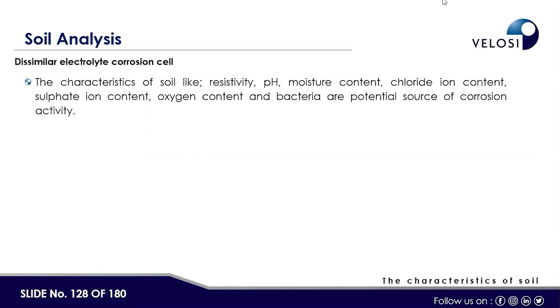Apart from resistivity, you also need to know the pH, moisture, chlorides, sulfates, and bacteria present. If we combine all these, an area with less than 1000 ohm-centimeter resistivity, pH of 4.5 or less, chloride content greater than 1000 ppm, and sulfate greater than 5000 ppm is considered very aggressive and very corrosive soil. This is typical near seawater, coastal environments, marshy areas, or sabkha soil.